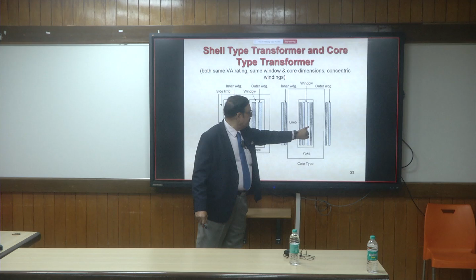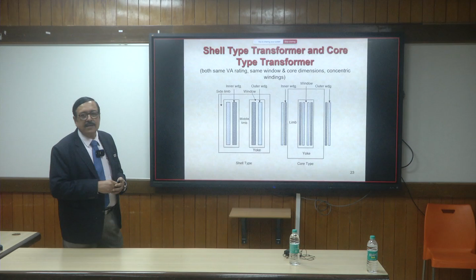If that happens, you'll find that the height is more for the core type, because now the yoke has to carry the entire flux, whereas here the yoke had to carry 50% of the flux. But you get much better cooling, because the surface area, what you had here, first of all, was embraced within the limbs. It was not getting 100% cooling. Now you have the same cylinder split into two 50% size cylinders. So the surface area is going to be much more, not double, but more than what you had. So you have much better cooling. So invariably in power applications, when we design transformers for power electronics, we select this. Shell type is only for very small power applications, quick assembly. None of us in the industry use shell type. It's all core type.